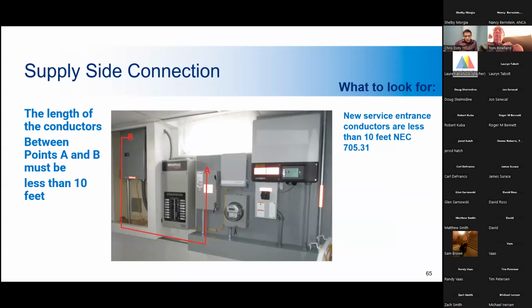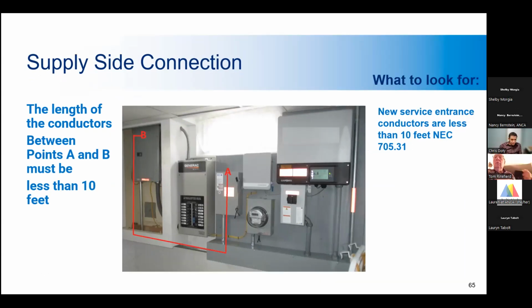Another thing in the code is it states that the length of the supply side conductors can be no longer than 10 feet unless other means are taken to protect them, such as current limiting devices. You can see here at A where the inverter output is fused and changed to service conductors, which are 60 amp rated, and they go over to the breaker panel through the conduit, and that length can be no longer than 10 feet.